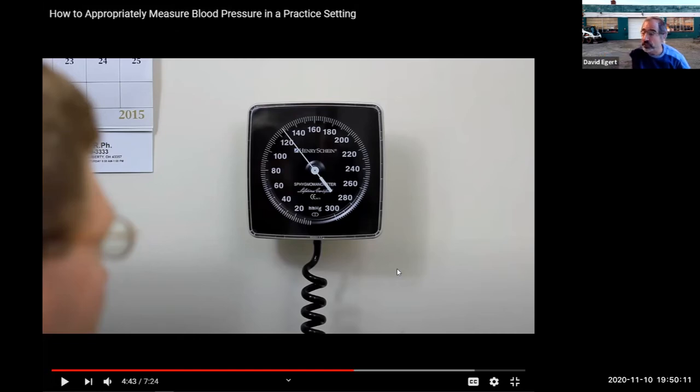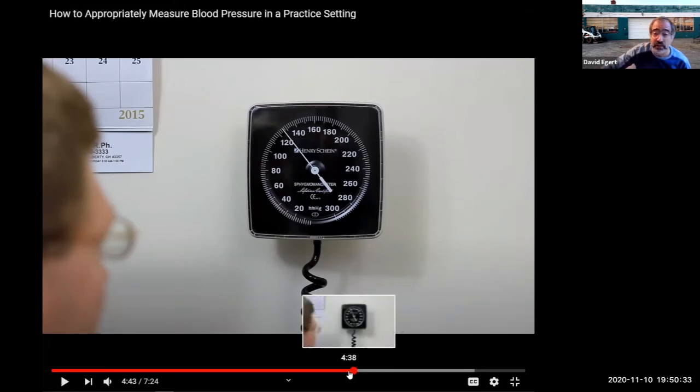So when you're seeing the little needles starting to pulse like that, it's not what you are paying attention to. It's irrelevant. The time you start to pay attention is when you hear the sounds begin. So make sure, again, because you can see as she's starting here, she has not hit systolic pressure, but we can already see that the changes of pressure above the cuff are actually causing these little undulations.